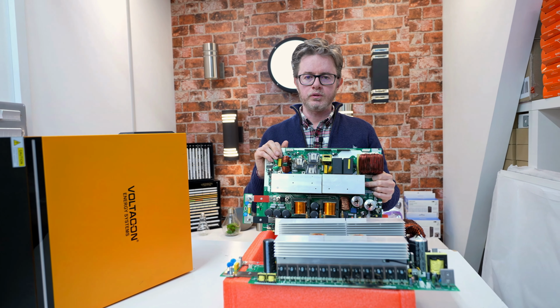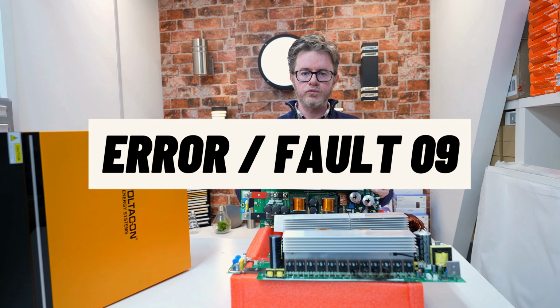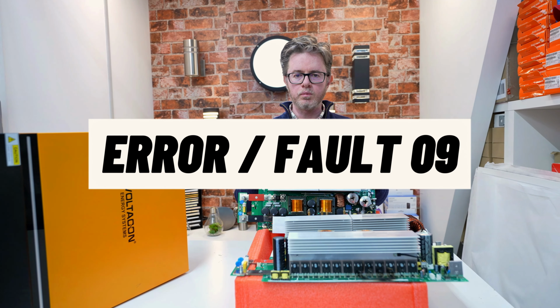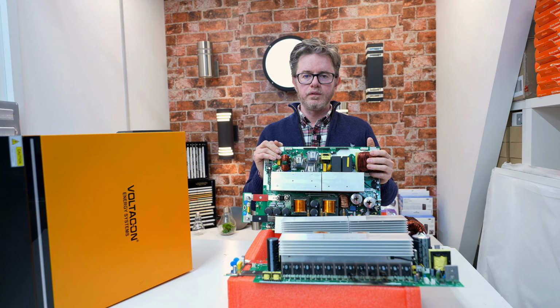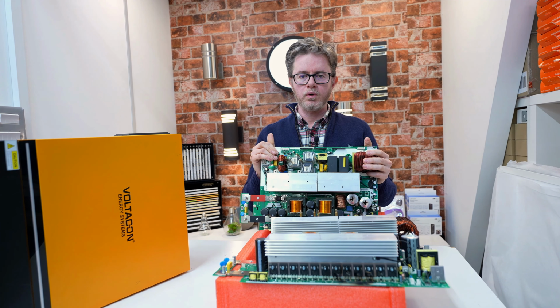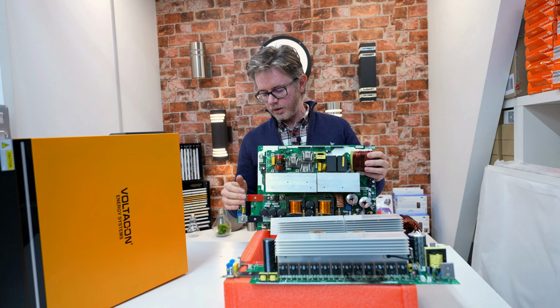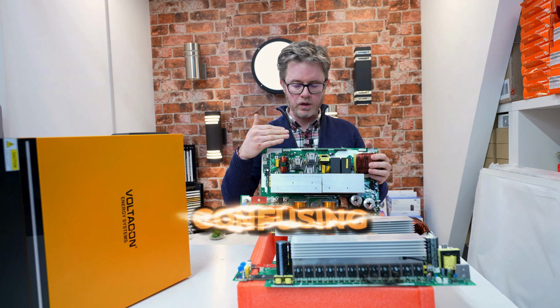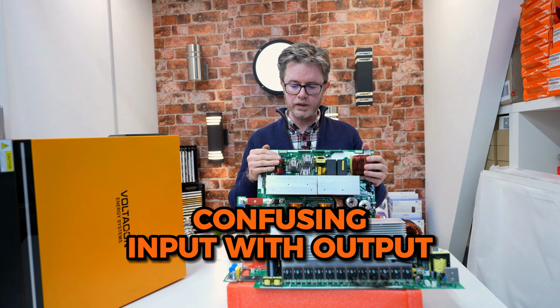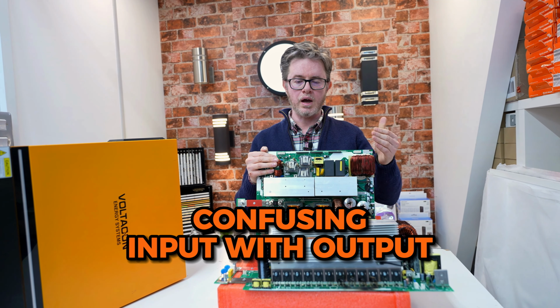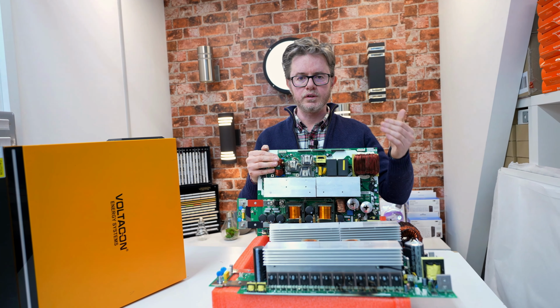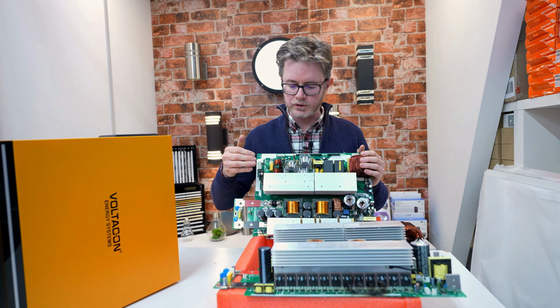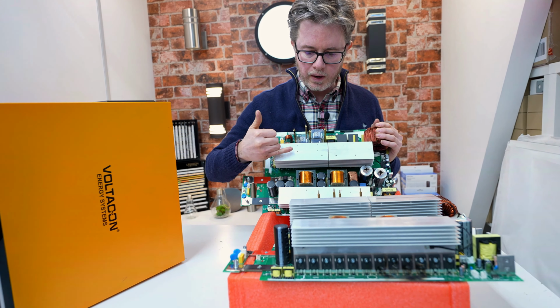Today we will talk about the error 09 or fault 09. This is the most common type of error. The number one reason why this is happening: many of the installers confuse the input and the output. If you connect the input to the output terminal of the inverter, this is going to blow up the DC link capacitors.